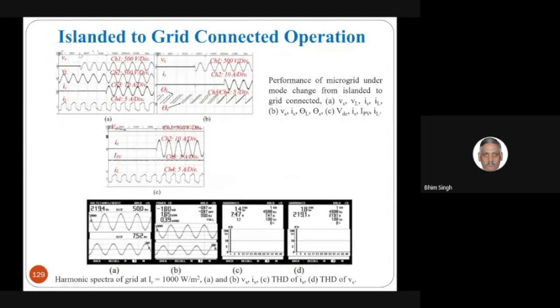And this is typically the synchronization. You can see that the load voltage and load current are not affected, even when the grid was not there. So when the grid appears after a few cycles, the inverter synchronizes to the grid, and the switch is closed. The grid current will start coming in, and you see how the angle matching takes place, as the grid voltage angle and load voltage angle are synchronized.